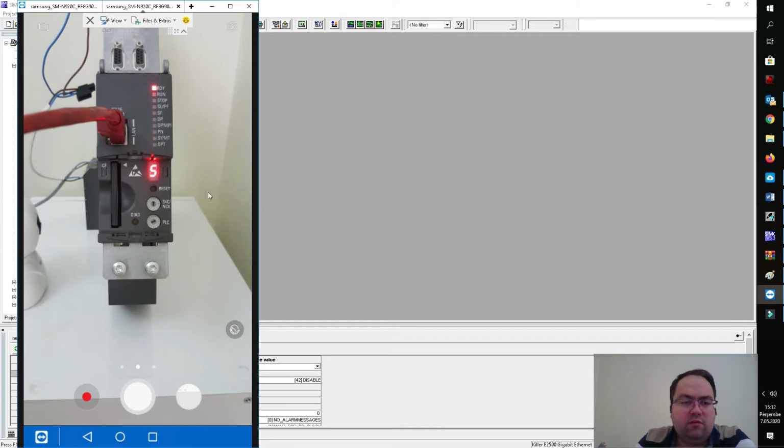For the factory reset function, you have to set your service switch to 1 and your PLC switch position to 3. After that, you can hit the reset button or switch the power off, and your CMotion will execute the factory reset.